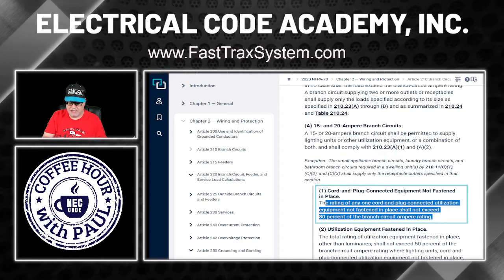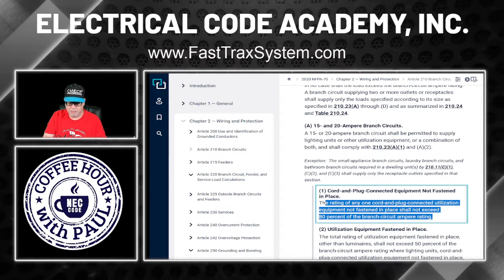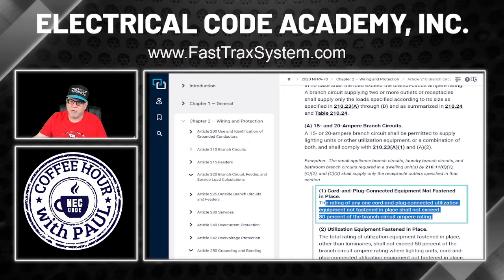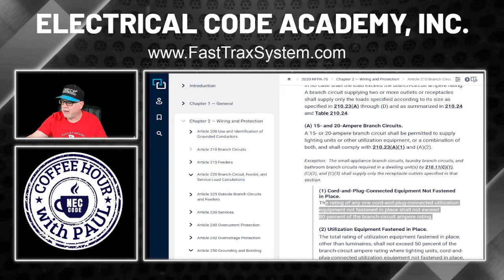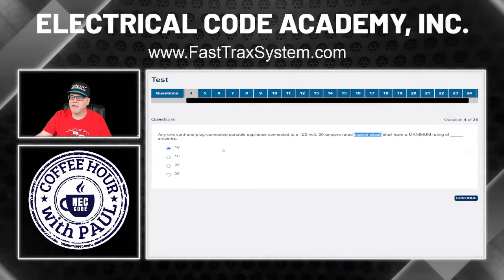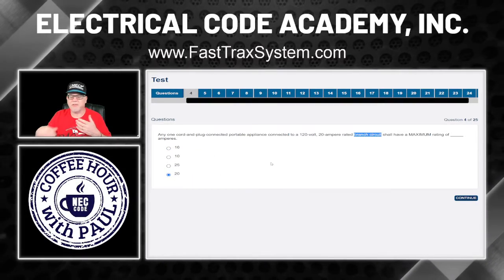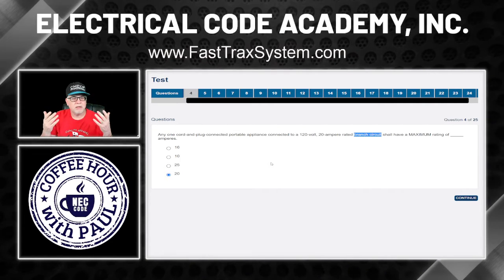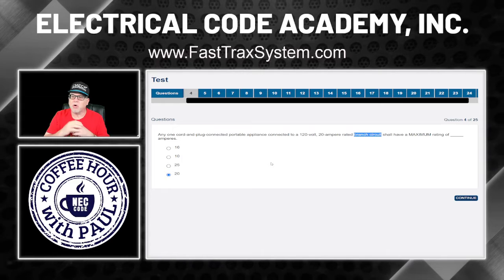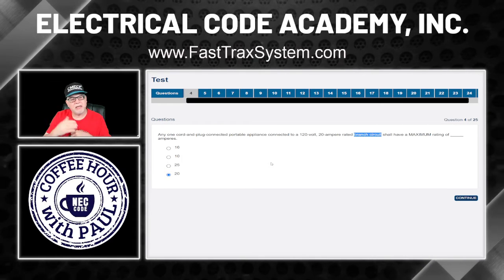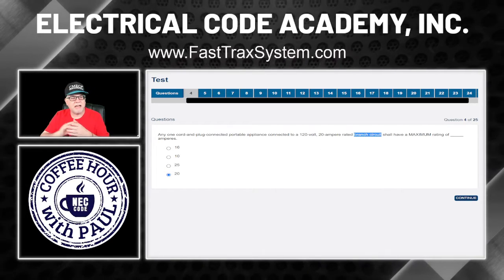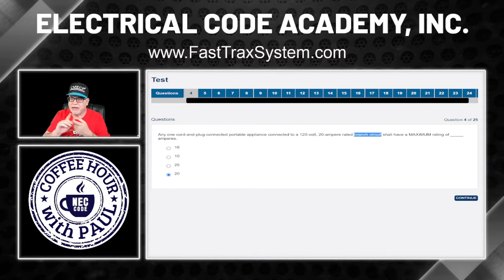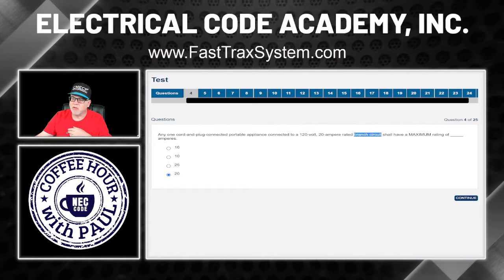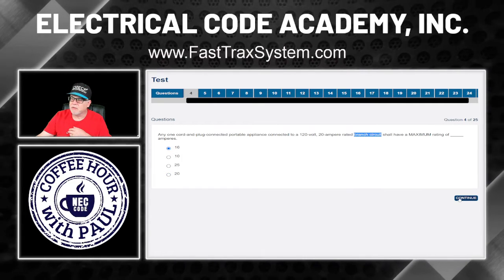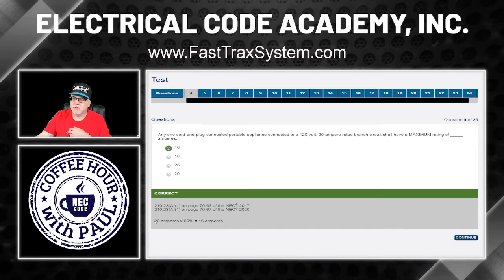But reading that, I'm going to do 20 times 80%, and that is 16. So I'm going to choose 16. So we originally clicked 20 because we're thinking, okay, it says the branch circuit rating, and that's true, 20 amp, you can put 20 amps on it. But if you have a cord and plug connected portable appliance plugged into a 20 amp, we just read what that said. In 210.23(A)(1), for any one, you have to limit it to 80% of that. So 20 times 80% is actually 16. So let's see if we're right. And there you go.